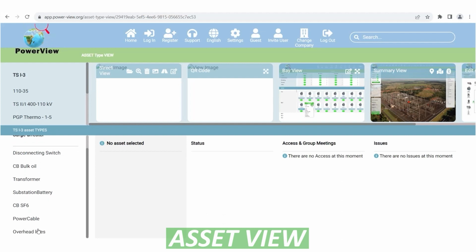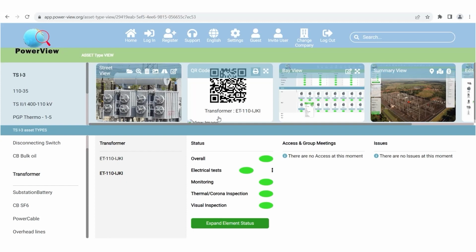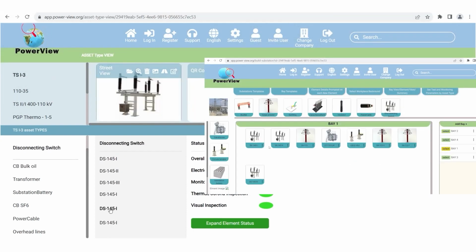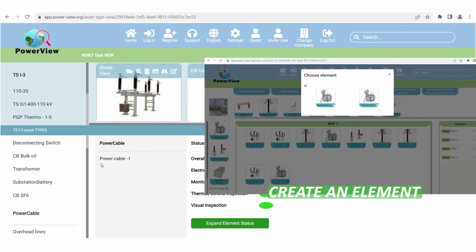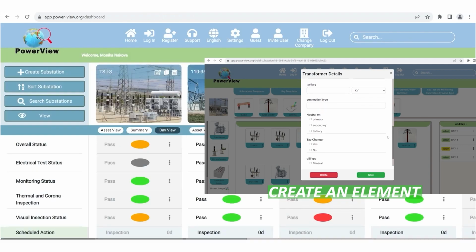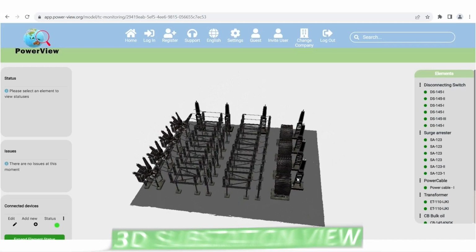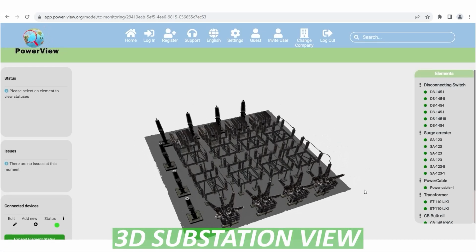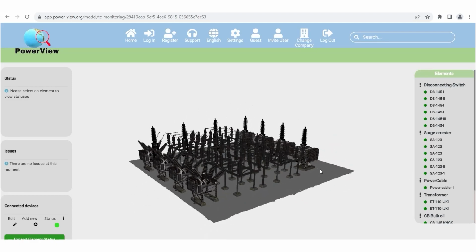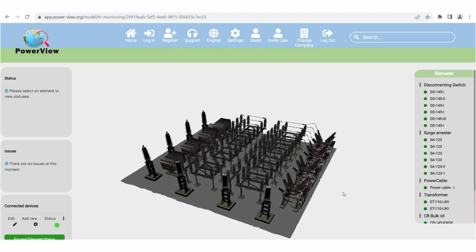Substation Digital is free software that analyzes and manages all this. A digital version of each substation element is created in this web-based software with all relevant parameters such as voltage levels, connection type for transformers, tap positions and other important elements from the nameplate and FAT report. Based on this, the software creates a digital model, out of several millions available, which has all the relevant electrical inspection list, with individual parameter trending and report and various alarm limits for each tested parameter according to international standards.